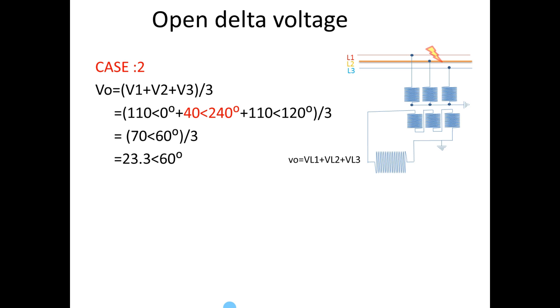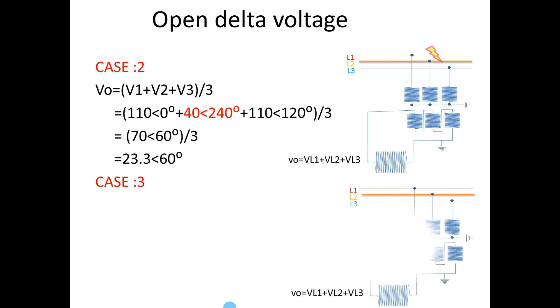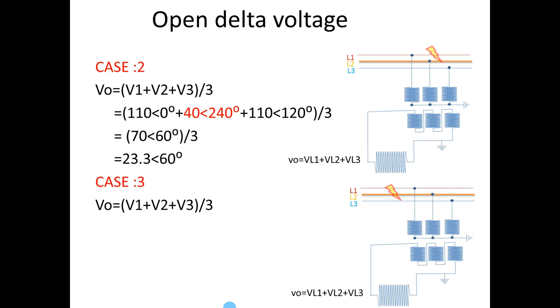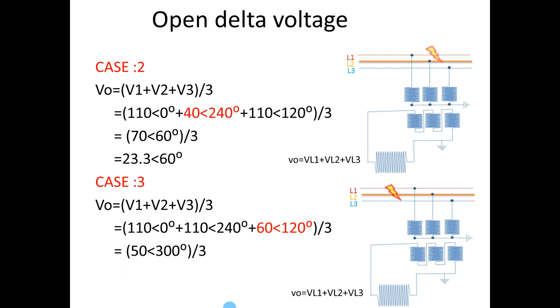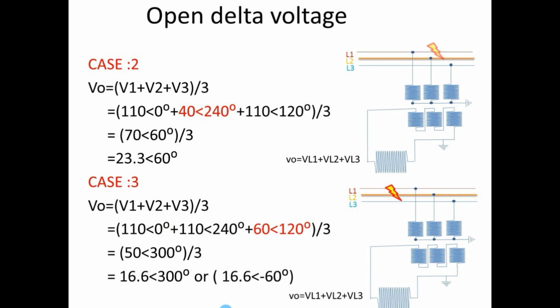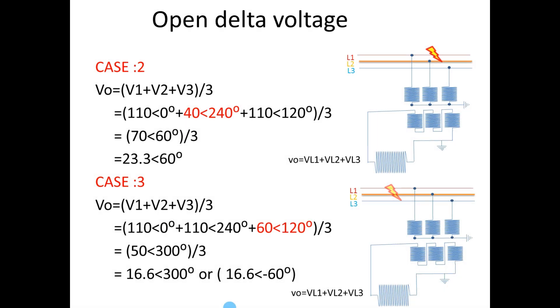Now I go for Case 3. Let us consider the fault on B phase. During this time, depending on the fault on B phase, the B phase voltage will get dropped. Let us consider the voltage on B phase is 60V. After making the calculation, the open delta voltage we get is 16.6V at 300 degrees or minus 60 degrees. We will note down all three phase voltages with angles.